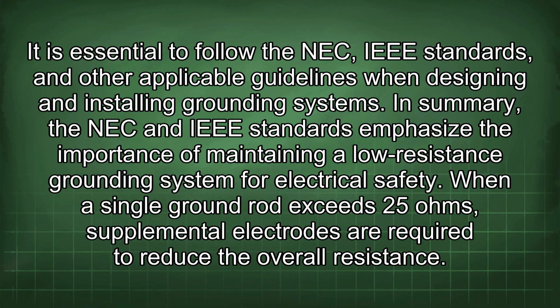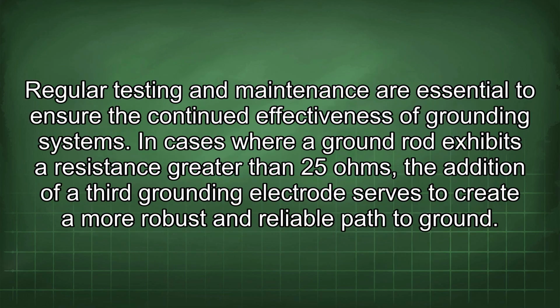When a single ground rod exceeds 25 ohms, supplemental electrodes are required to reduce the overall resistance. Regular testing and maintenance are essential to ensure the continued effectiveness of grounding systems. In cases where a ground rod exhibits a resistance greater than 25 ohms, the addition of a third grounding electrode serves to create a more robust and reliable path to ground.